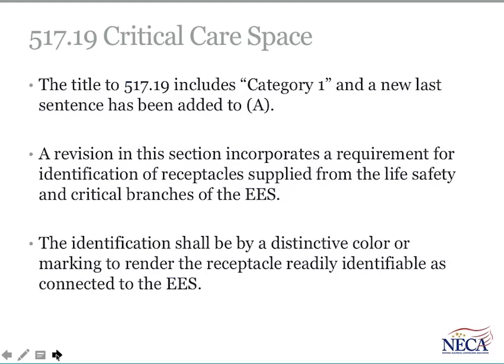Section 517.19, once again, the word space replaces location in this section. And what you'll also see here, in parentheses, is Category 1 used in here, with the revisions necessary to incorporate the changes we talked about earlier to the definition and the categories, aligning with how they address that in NFPA 99. There's another revision in this section to clarify that the identification of the receptacles in the critical care space has to be by a distinctive color or other marking to render them readily identifiable as a receptacle connected to an essential electrical system.